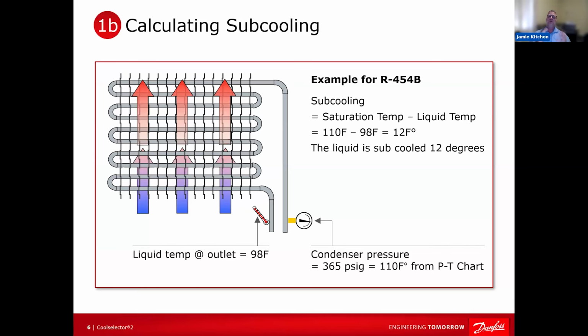And as you remove heat from it by basically rejecting heat to the air or water, it condenses and condenses and condenses until you end up with 100% liquid. Now your latent heat exchange is stopped and you have 100% liquid. And because that liquid is still warmer than the air, you're going to start to subcool. The more subcooling you have, the more the temperature has dropped below the point that it has condensed.